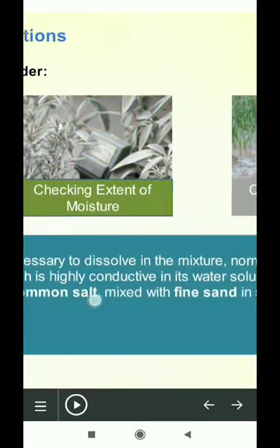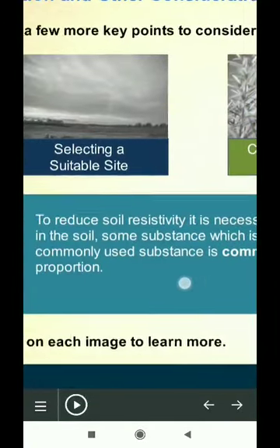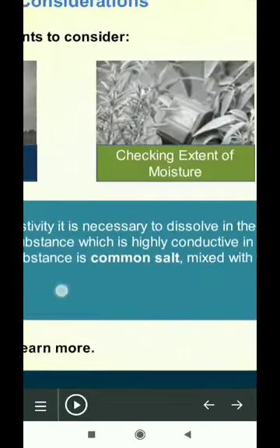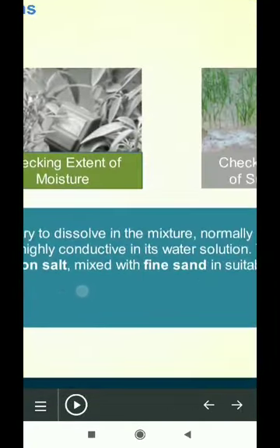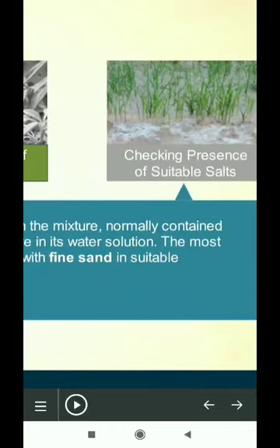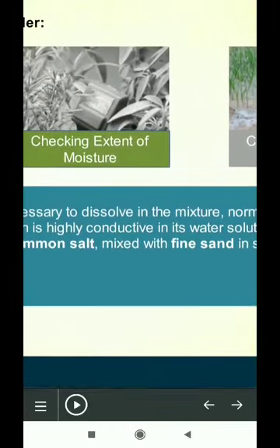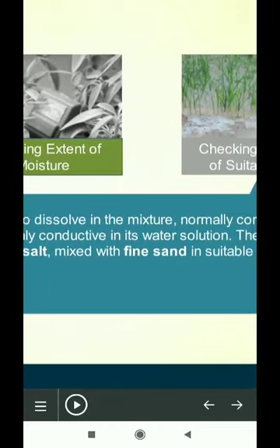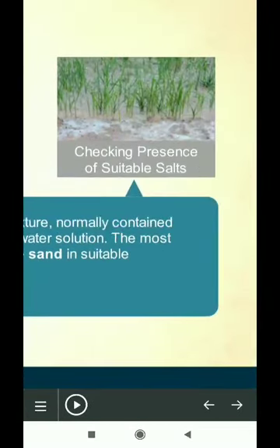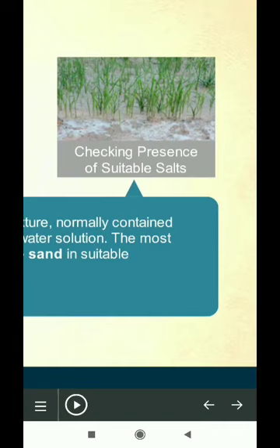To reduce soil resistivity, it is necessary to dissolve in the mixture normally contained in the soil some substance which is highly conductive in its water solution. The most commonly used substance is common salt mixed with fine sand in suitable proportion.